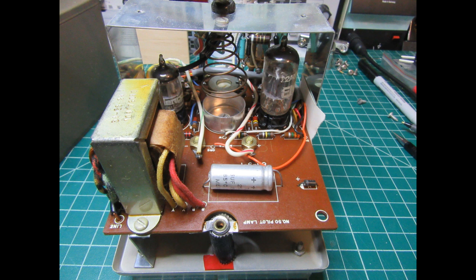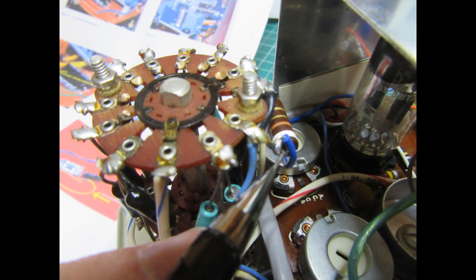And all the other capacitors are just non-critical ceramic disc capacitors, which again tend to not go bad, and even if they drift a little bit in value, the values are not critical, so you most likely will not have to mess with those either. One thing that is almost certainly going to need some attention, especially if the meter hasn't been used recently, are the contacts on the selector switches. And in this view, the rear deck of the range switch is visible, taking up almost half the photo. And you can see the wiper ring on it is almost black with oxide.